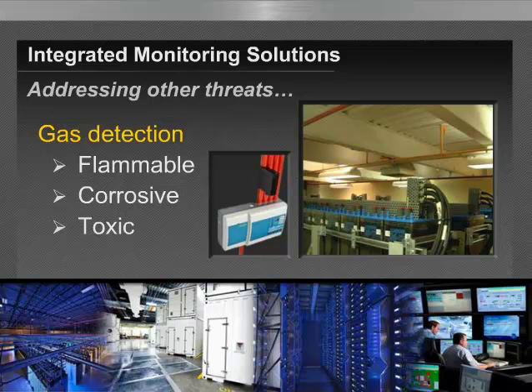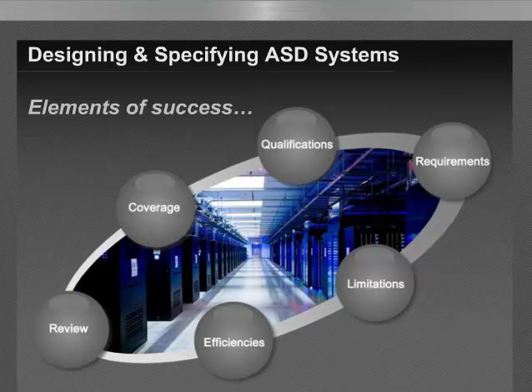And so, designing and specifying aspirating detection systems, we look at various things in terms of what we would consider the appropriate method of designing. A properly designed air sampling aspirating detection system is paramount for the proper operation of the system and meeting fire protection objectives. So the design specification should take into consideration the qualifications of designers, installers, and commissioning technicians, ensuring that they're authorized by the particular manufacturer's brand.